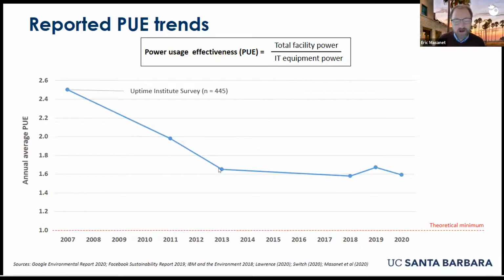A lot of work has gone into reducing PUE. How do they do this? More efficient UPS systems and much more efficient cooling systems. But the Uptime Institute has found that PUE gains have really slowed for about the last half decade or more, hovering at about 1.6. That means for every unit of power that goes into the IT equipment, there's 1.6 units going into the overall data center. So this is a success story, but it's also a challenge for the industry moving forward.